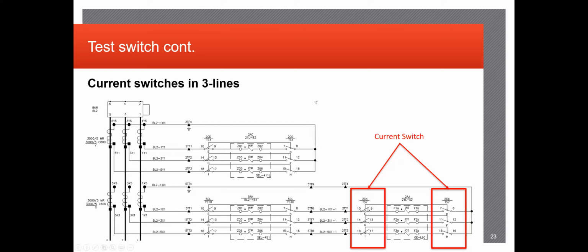So going back to putting the breaks in these circuits, especially with the current circuits, it's all about flow, how it goes in and out of each relay. If you were to break the circuit here and here, you can specifically identify that 2TT1 goes to 10 on test switch 7. If it goes to 9 on test switch 7, that's a problem, because that means the test switch is actually backwards and won't properly short the circuit out if it's opened up and energized.